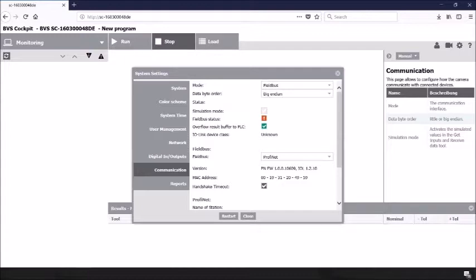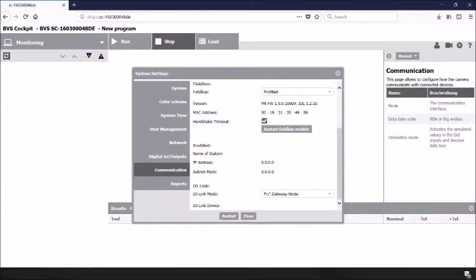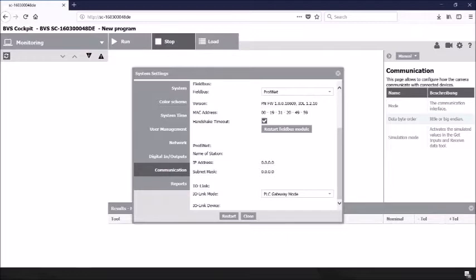Regardless of which version of the camera you choose to use in field bus mode, you'll notice the top of the tab will be similar. You will have the choice of selecting simulation mode as discussed previously. You will also have a field bus status icon telling you the connectivity status of the field bus connection. You will also have an overflow results buffer to the PLC that you can check. It is advised that you always keep this box checked. When moving on to the field bus settings, you'll notice you have a drop-down to allow you to select which field bus you plan to use.